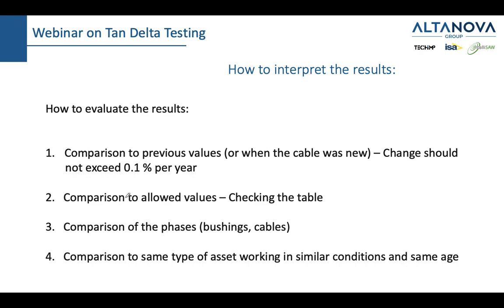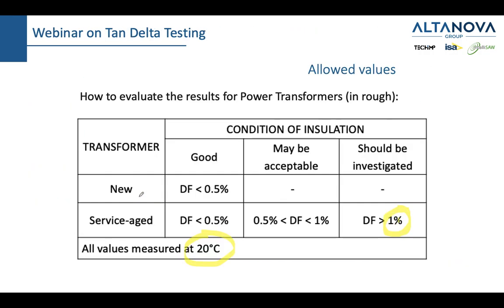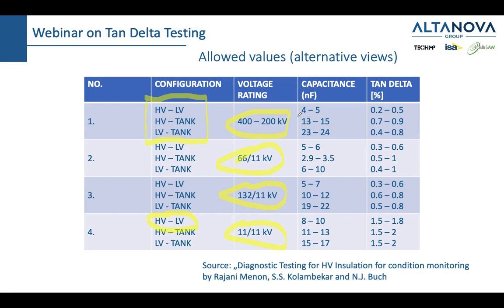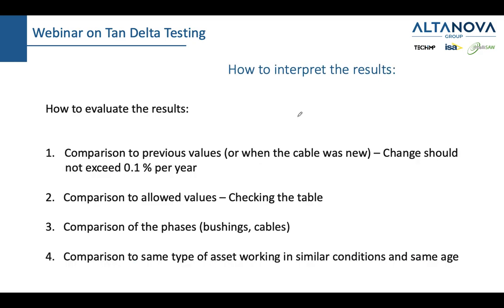The next way to evaluate results is comparison to allowed values. If you use the table which we have shown before, like this one, the number needs to be smaller than 1 as a general rule, or if you want to be more exact, you can take a look at this table and compare it to that. The third way would be comparison of the phases. If you are measuring tan delta on bushings, because you will see later that we don't just measure tan delta on the body of the transformer, we also measure it on the bushings. If you measure on three phases, A, B, and C, you expect to get the same numbers, especially if the bushings are the same, installed at the same time and from the same producer. If a certain bushing has a higher tan delta, then what you will probably do is a frequency sweep. But we will talk about that in our next session.